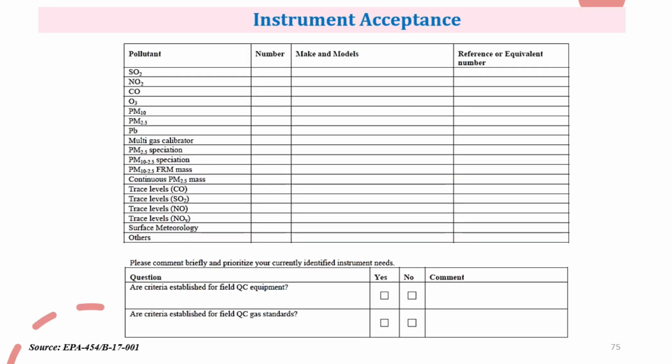A typical instrument procurement acceptance should include factors such as compliance with local environmental conditions and government requirements. This ensures that the instrument meets regulatory standards and can be procured and operated accordingly. The acceptance process should cover all aspects of calibration, functionality, accuracy, and adherence to required specifications to ensure the instrument's proper use in the field.